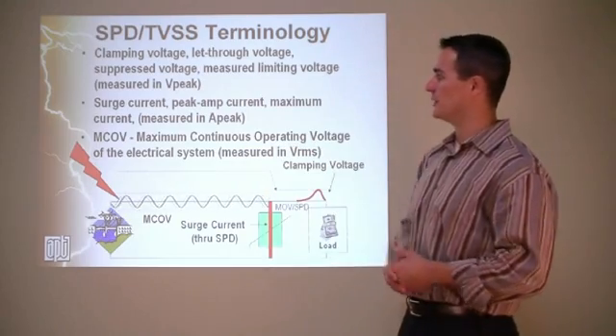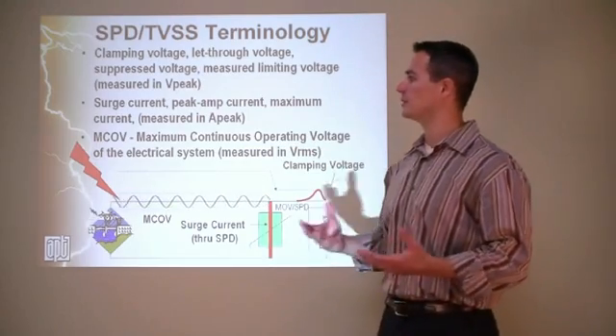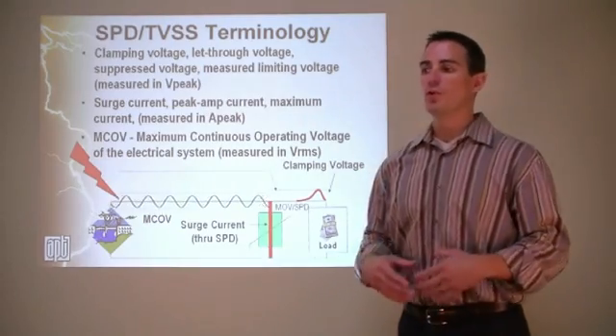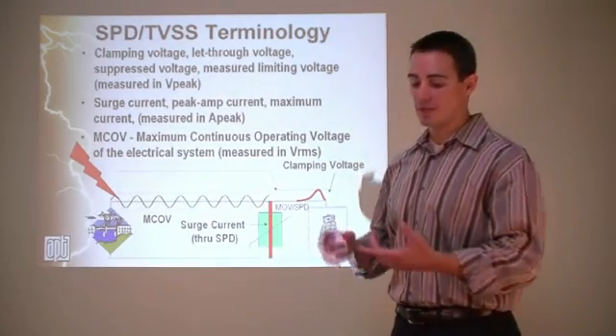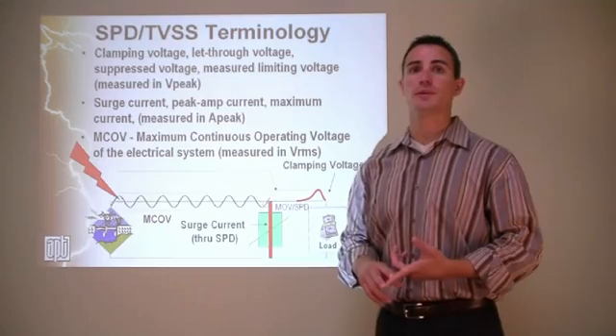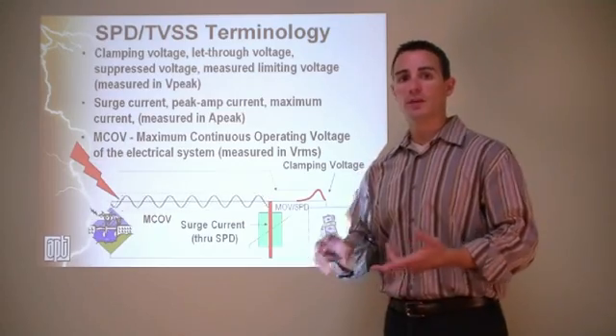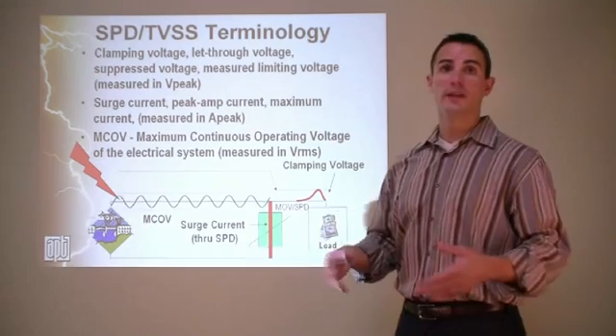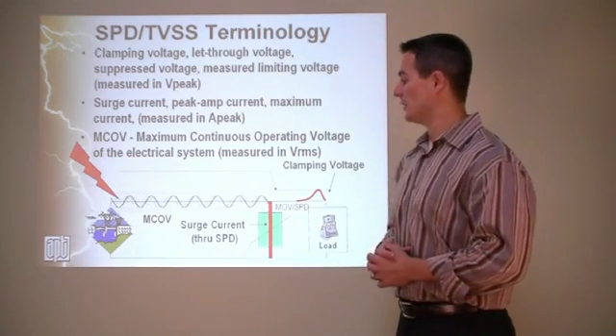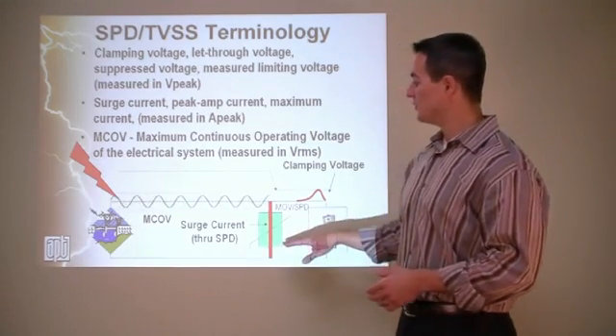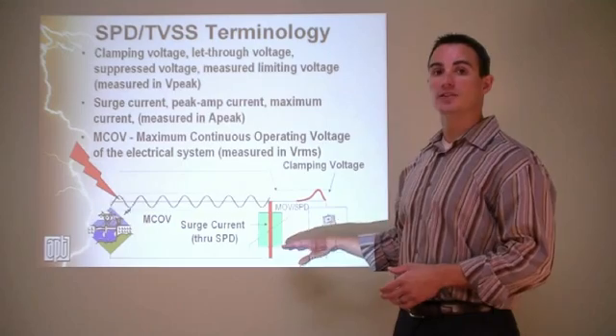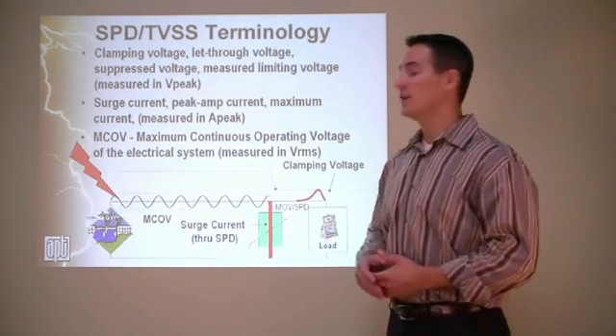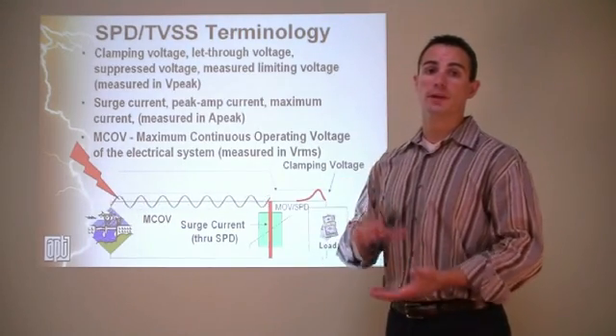We have MCOV, which stands for maximum continuous operating voltage. In surge environments, we talk about two MCOVs: the MCOV of the SPD itself, and the MCOV of the electrical system — 120, 277, whatever that may be. The MCOV of the SPD is always going to be larger than that of the electrical system, because we don't want them bumping into each other.